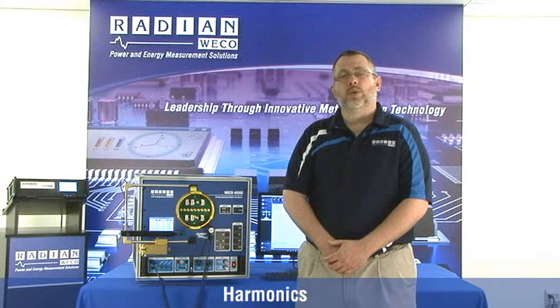Another available test recently introduced into our 4000X series test board and our RX family of reference standards is fundamental only testing. In this testing scenario, we replace a pure sinusoidal waveform with a harmonic waveform, then measure the fundamental waveform only, disregarding the effects of harmonics. This is a feature being introduced into the global meter market, and WECO is the front runner in helping meter manufacturers develop and test these meters.